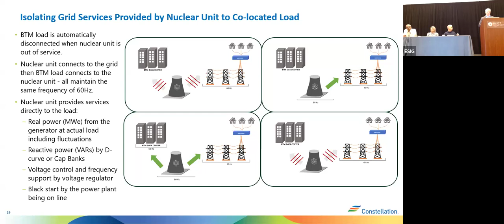Then in order to bring power into service for the data center customer, we match voltage and frequency with the equipment within the nuclear plant to that of the grid. The nuclear plant connects to the grid, and only after the nuclear plant is connected to the grid can the customer be brought back into service. And then once again, if for some reason the power level at the nuclear plant dips below the amount of load that's being requested by the data center customer or other large load, the load will disconnect in that case. So that's how a fully isolated load works in our design.